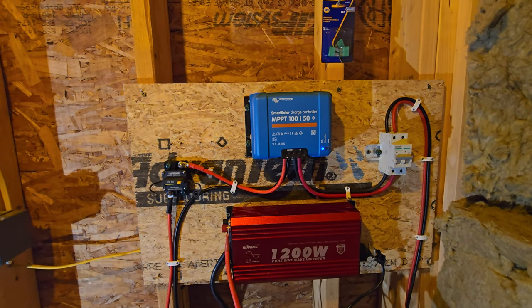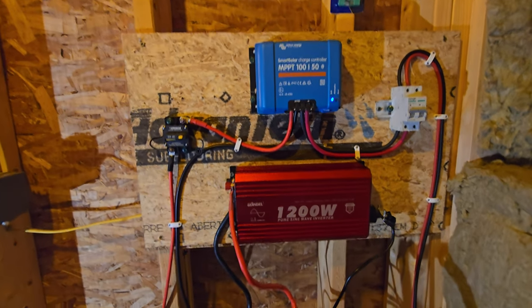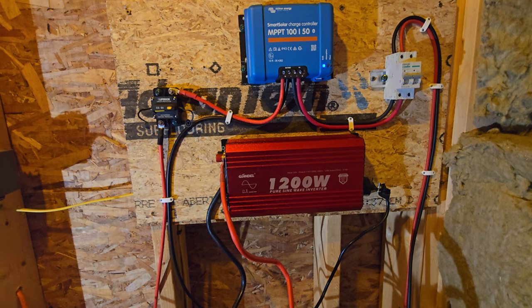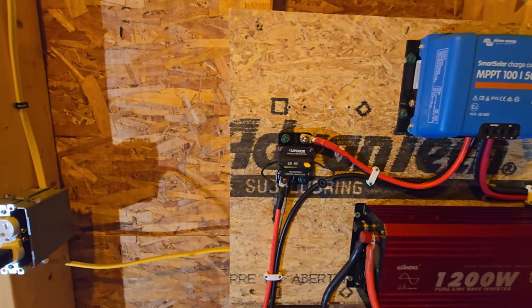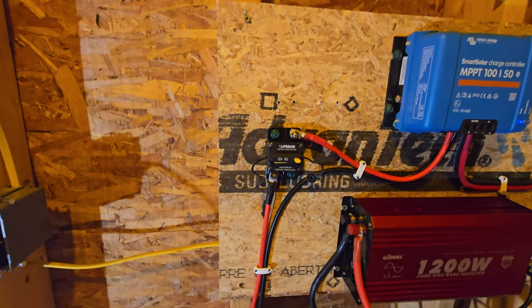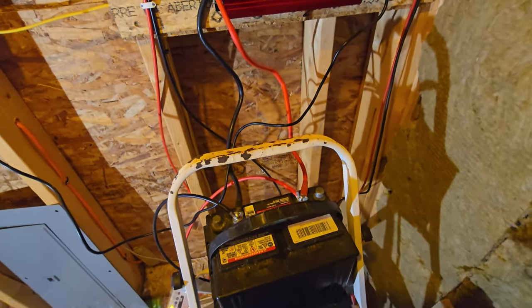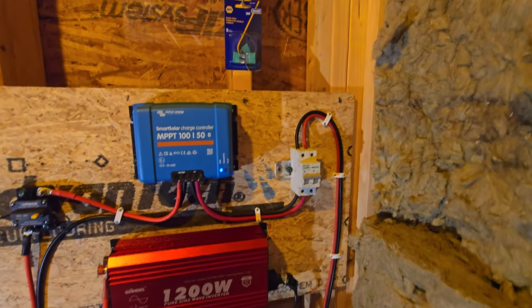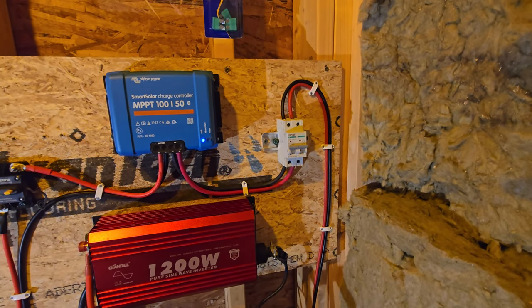I got myself a Victron Smart Solar 100/50 MPPT and a Giandel 1200-watt inverter. I've got the breaker going to the batteries — one 12-volt battery for now. They're a little long; I might tweak this more. And then I've got the shutoff for the solar panels coming through this breaker here.